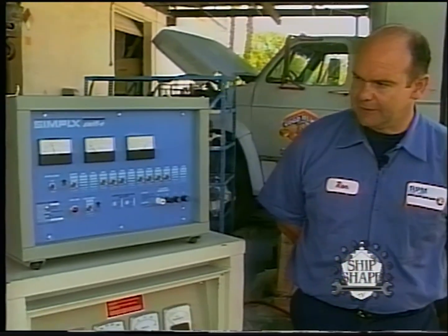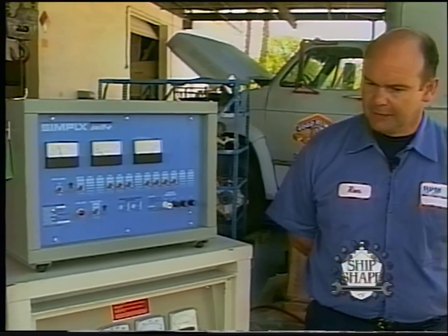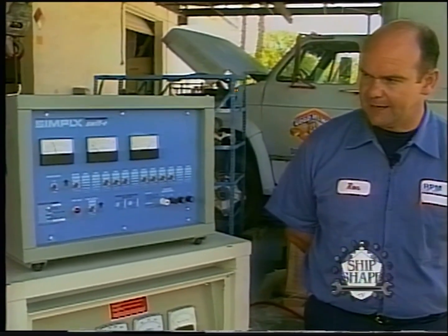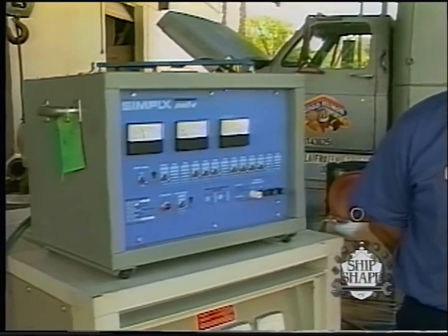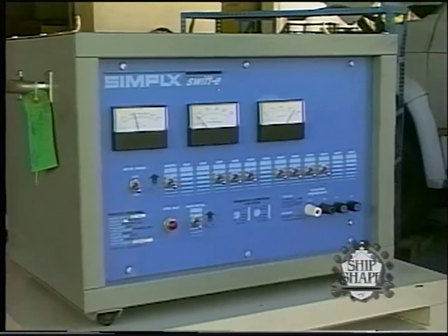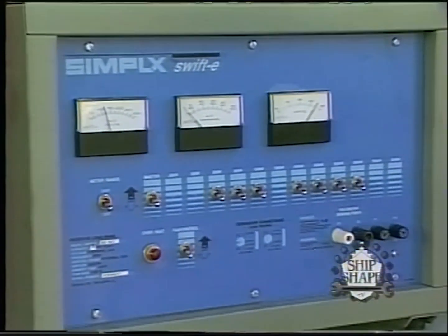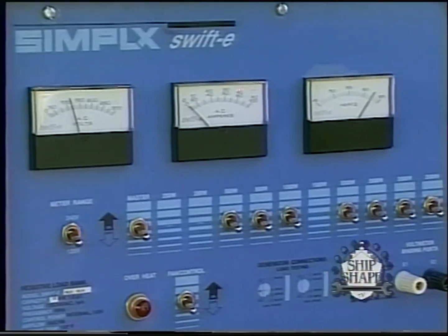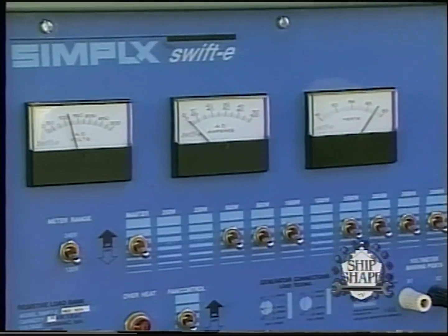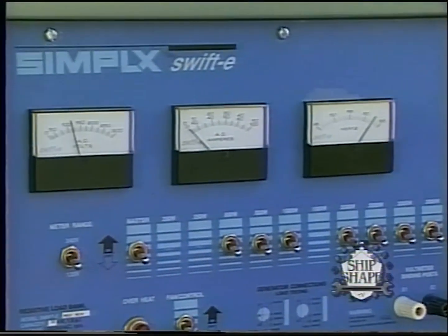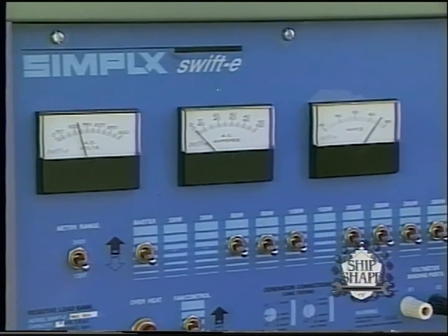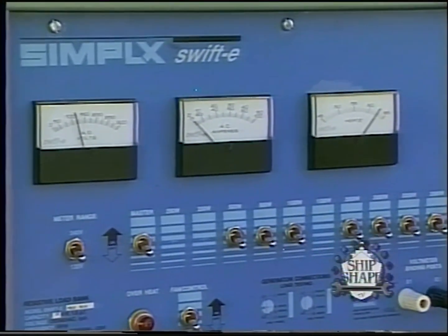Now we've got some readings going on the dial here, Ron. Can you explain what we have going on? Sure. The first one on the left is the AC volts coming out of the generator. This generator is set up as a straight 120-volt generator. In the center we've got the AC amperage, which is the load on the generator itself. At the moment the load bank is switched off, so there's no load. On the right we have the frequency, measured in hertz, of the generator output.